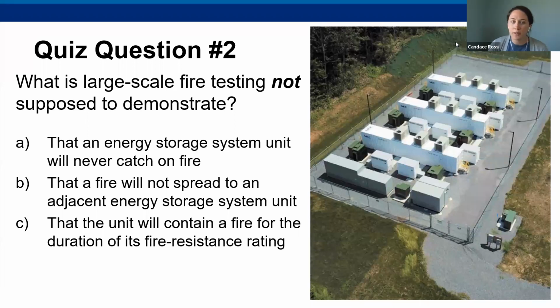All right, so it looks like we have mostly a consensus. The answer is A. So large-scale fire testing is not supposed to demonstrate that the system will never catch fire, rather that it will show that if it does, it will be contained as necessary. And also pictured here is a 20 megawatt system in Stillwater, New York, just north of Albany. So there's an image of a system that's currently installed.